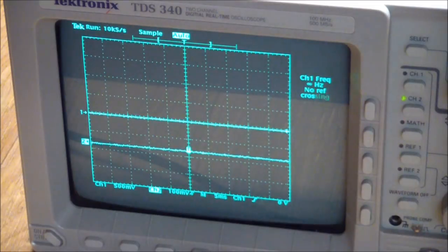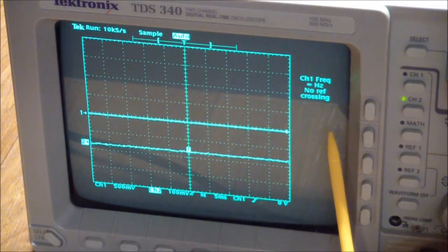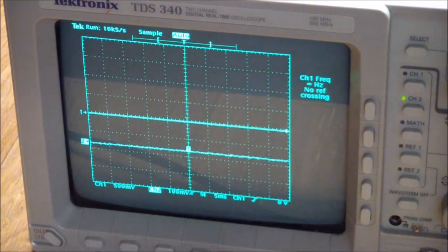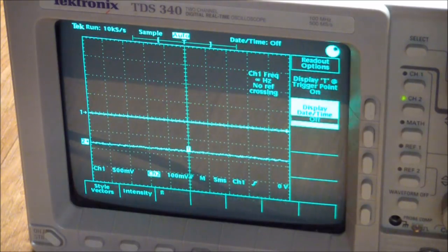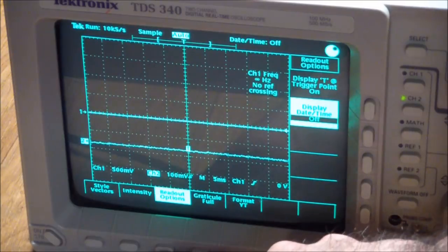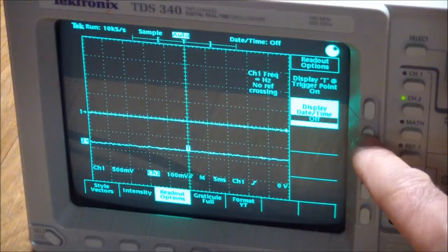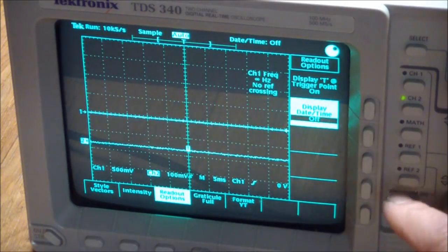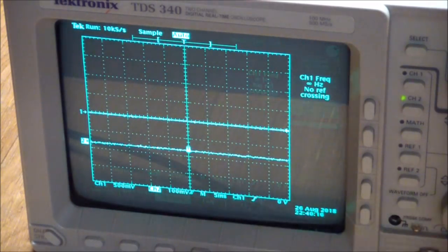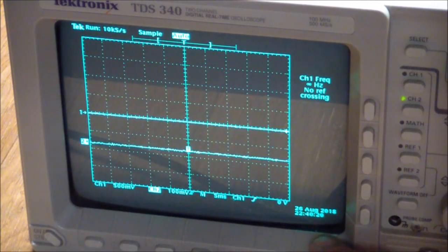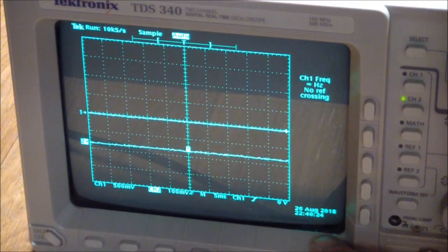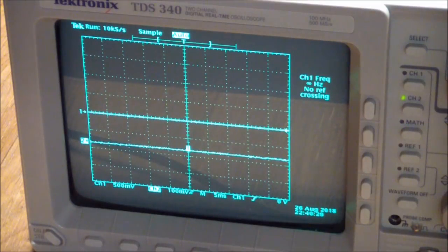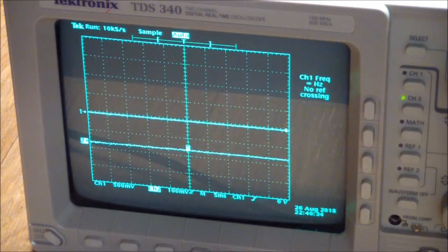Well obviously at some point somebody turned on the channel one frequency measuring part and it looked like it retained that. So let's go in and see if we can display the clock. Readout options, display time, set to off so let's turn that on and back out of here. And it's a few minutes off but it's kept the time. I don't know how long this thing's been dead and unused and not powered up but looks like the battery in the RTC module is still good.